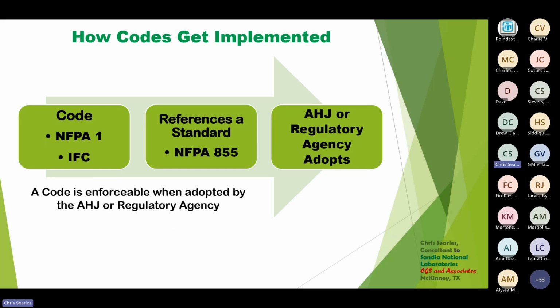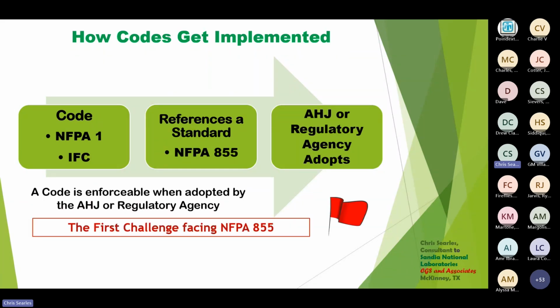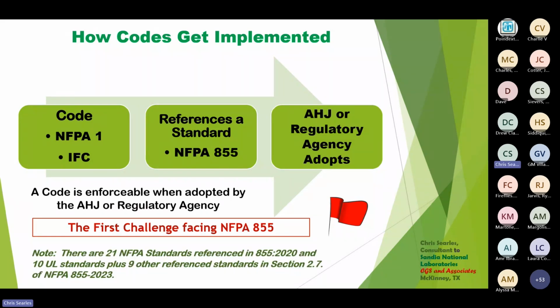A code is enforceable, as I said, when adopted by the AHJ or regulatory agency. This leads to the first challenge facing NFPA 855, the first red flag, if you will. As I mentioned earlier, there are 21 NFPA standards referenced in 855-2020, plus 10 UL standards and 9 other reference standards in section 2.7 of the most recent 855 standard.